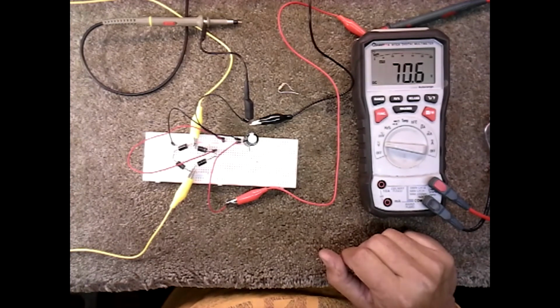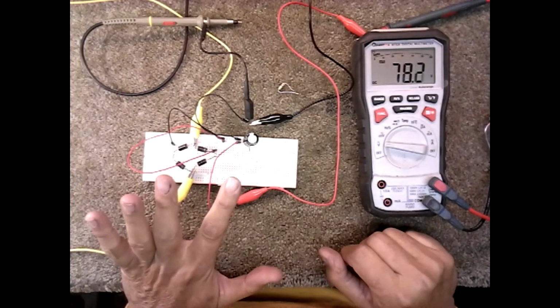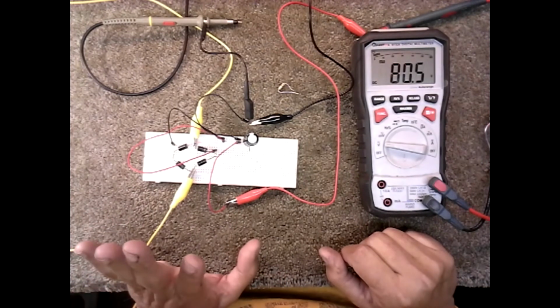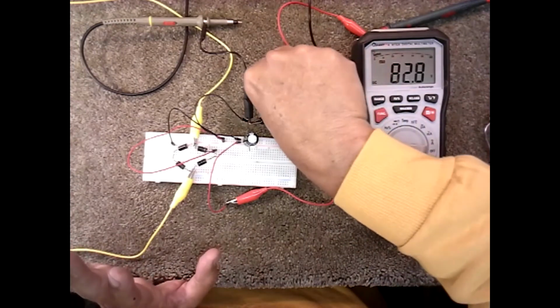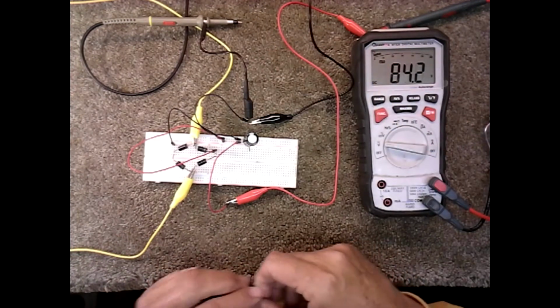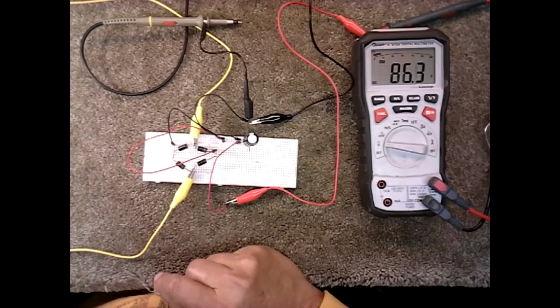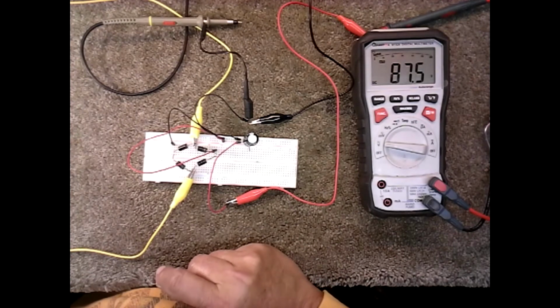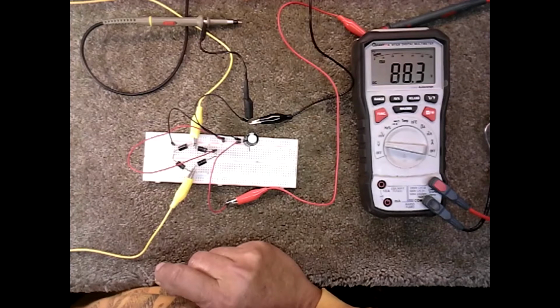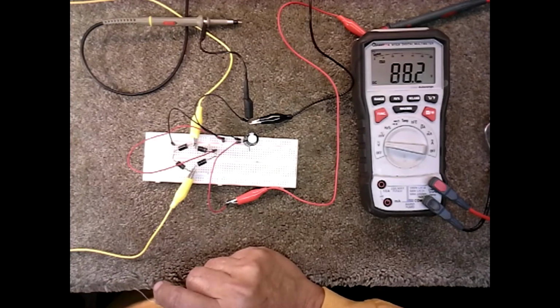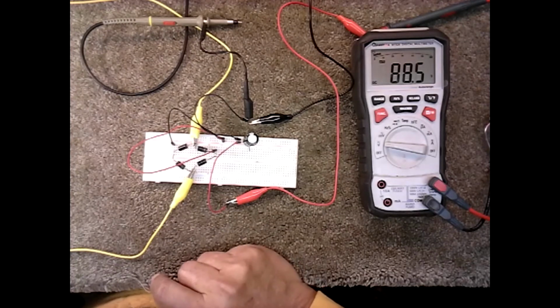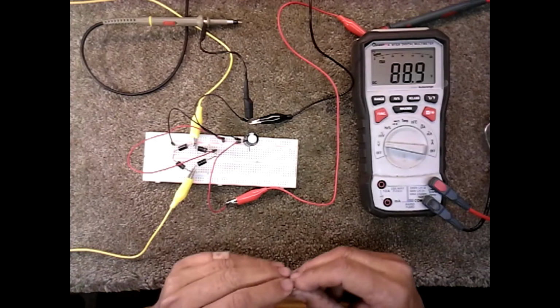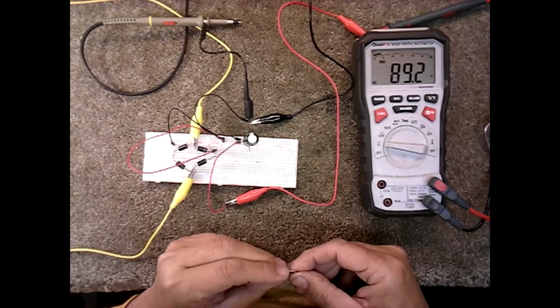That voltage is a ghost voltage. It's there, it's real, it's charging this capacitor, and all of that is actually happening. But it's still a ghost voltage because it has no current capability. If I bring the voltage up to where I can see the current on my meter, I have 20 milliamps of current. 0.5 watts is being consumed in this circuit to keep that capacitor charged.